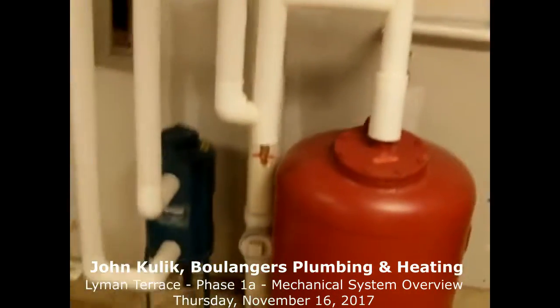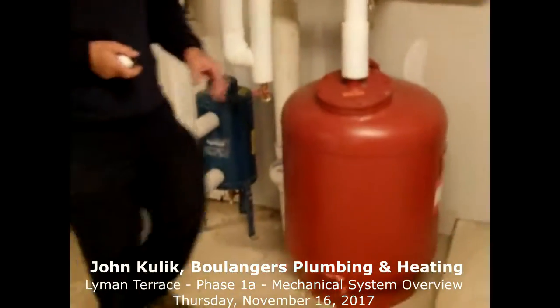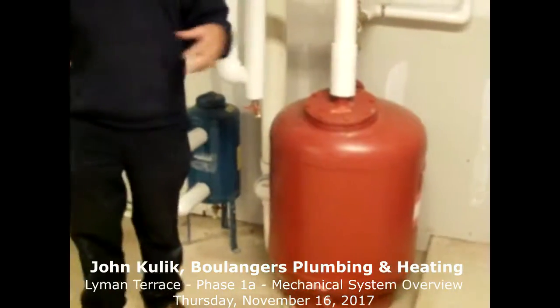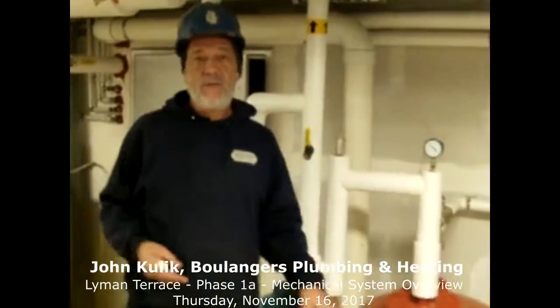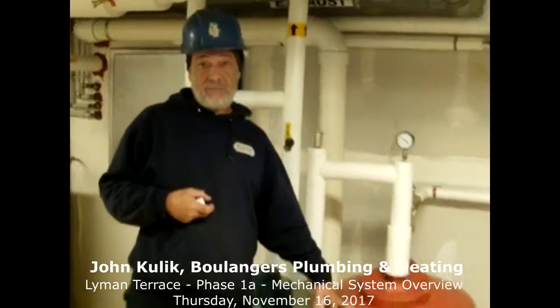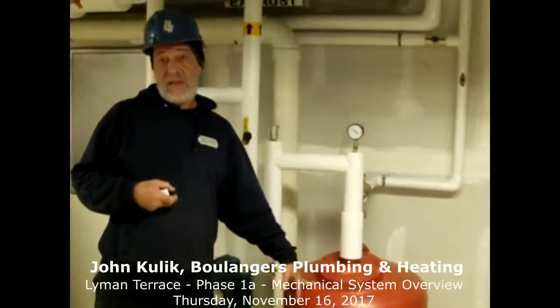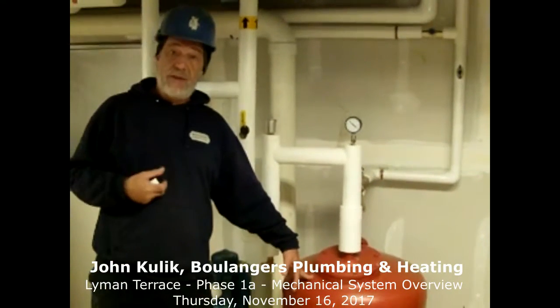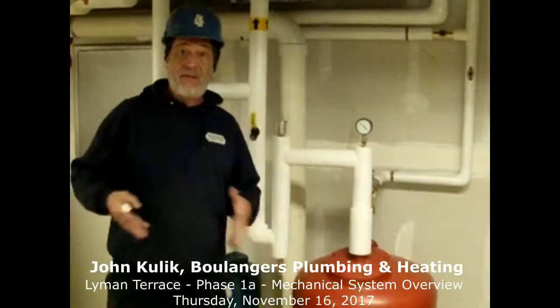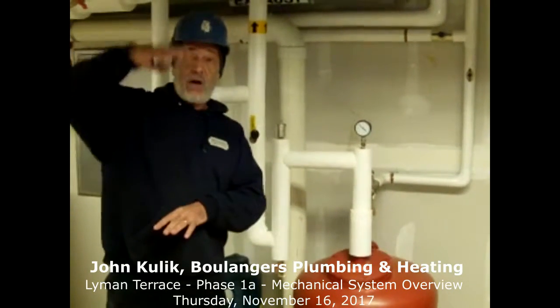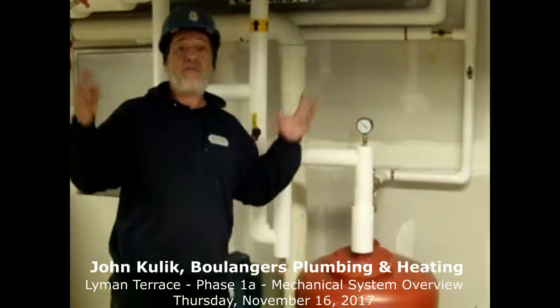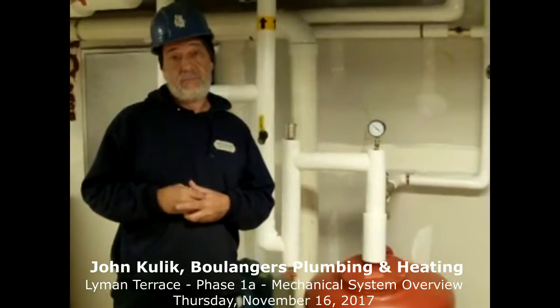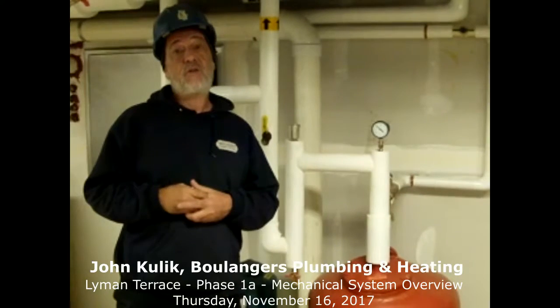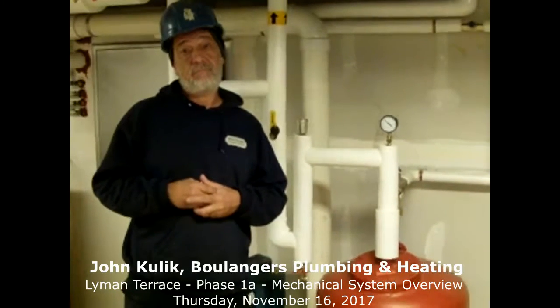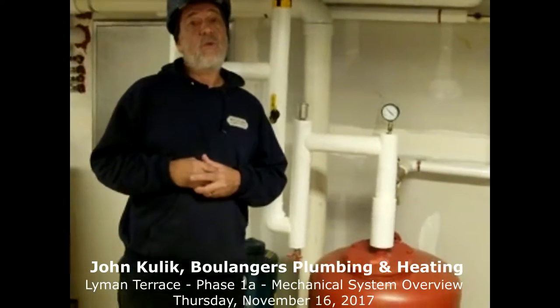So let's talk about these tanks over here. What are we looking at here? We're looking at a thermal expansion tank. When water heats up, it expands in volume. There's a bladder style tank here, air on one side of the bladder, water from the system on the other side. As it heats up, it expands. The bladder's air acts as a cushion, allowing the system not to overpressurize. And that's for the heating system side? Correct.